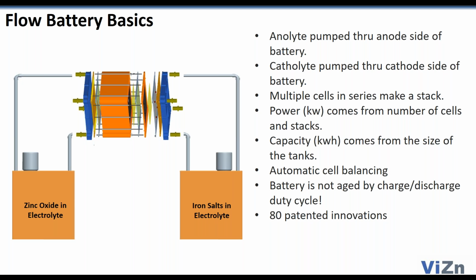We have a relatively simple cell design. Those cells are stacked together to make a stack. Our battery stack is 30 cells, roughly 3 foot by 3 foot by 3 foot, weighs 900 to 1,000 pounds for a battery stack. We can get as much as 20 kilowatts out of one battery stack.